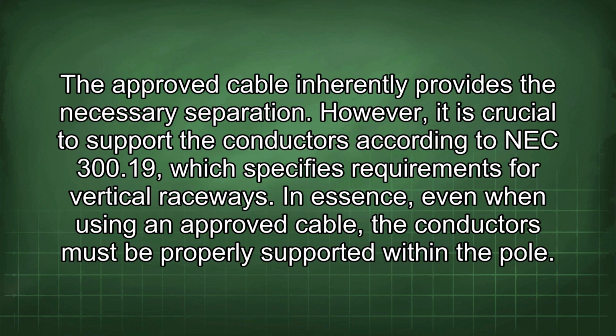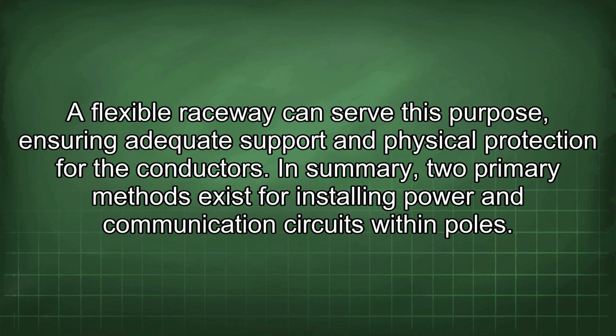However, it is crucial to support the conductors according to NEC 300.19, which specifies requirements for vertical raceways. In essence, even when using an approved cable, the conductors must be properly supported within the pole. A flexible raceway can serve this purpose, ensuring adequate support and physical protection for the conductors.